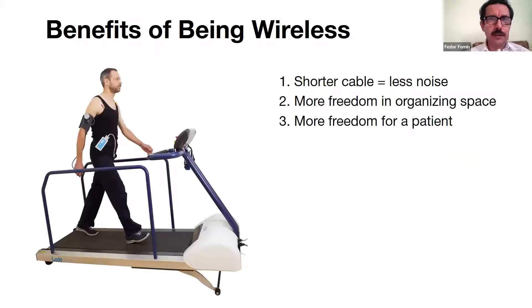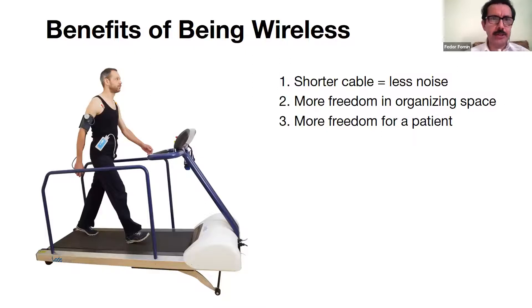As Nikolai Smirnov underlined, our device is wireless. For simple ECG, it may not be obvious why you need wireless. But when you perform exercise stress testing, especially on a treadmill, a person needs freedom of movement. If you are connected to a PC, your movement can lead to detaching the device or causing false errors in equipment performance.